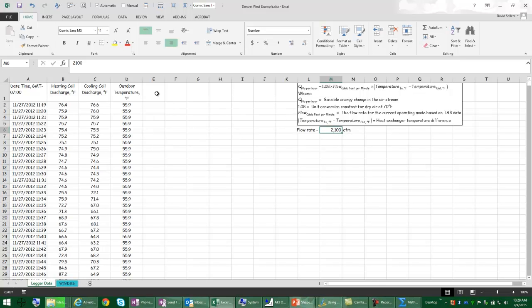And so let's just stick that formula in here. So the BTUs per hour is basically equal to 1.08. Now, a little subtlety here. In Denver, that correction factor, that factor right there, is the 1.08 in this equation.